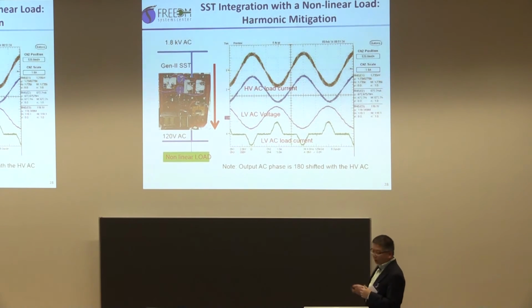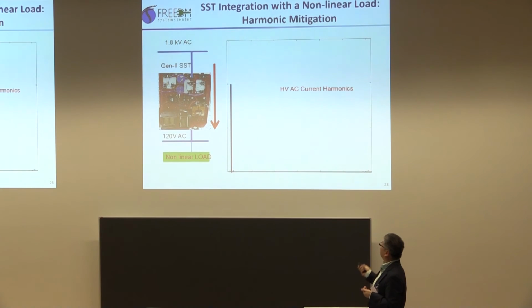Harmonic mitigation is another benefit: if you have a nonlinear load on the low voltage side, the harmonics will be blocked by this unit and won't propagate back into the high voltage system, providing a lot of economic value. So when we introduce this new technology, a typical question is about cost and reliability, which is hard to answer directly. But you can look at other benefits the new technology brings to the grid, like the high voltage side being only 60 hertz with no harmonics.